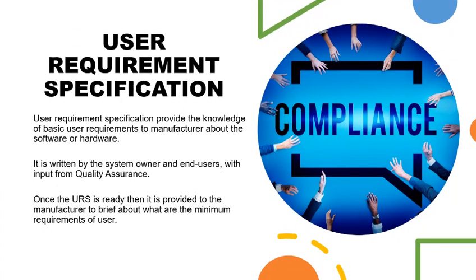Now we will discuss what is user requirement specification. User requirement specification provides the knowledge of basic user requirements to the manufacturer about the software and hardware. For example, from a quality laboratory, if you are planning to procure an HPLC instrument with software, you need to elaborate the basic requirement of how the instrument performs the chromatographic analysis and how the software acquires the data for processing and reporting.